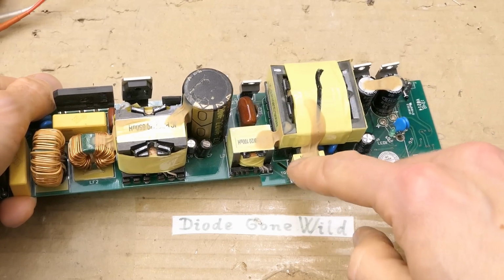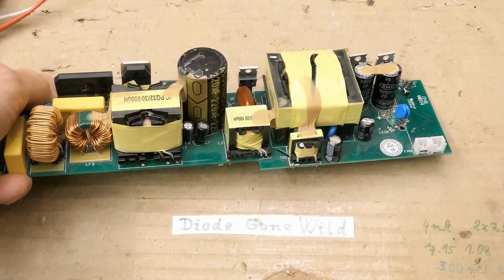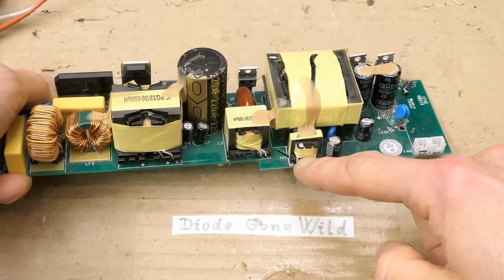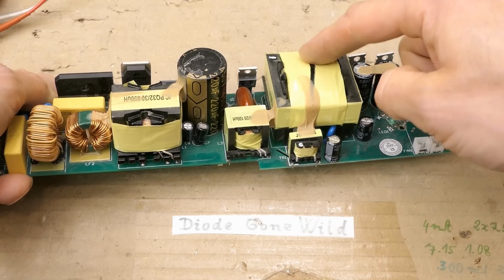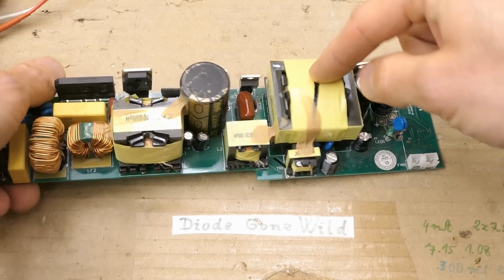Even though sometimes this one is skewed by the circuitry connected to it, so a low number of rings doesn't necessarily mean short turns. And the power transformer - you're typically ring testing just the primary.